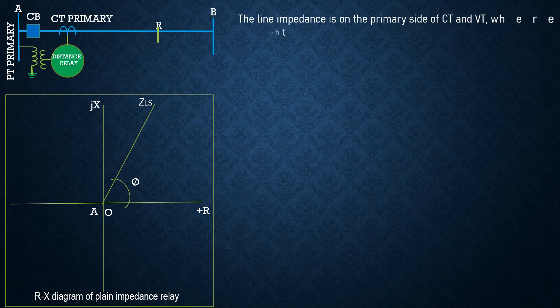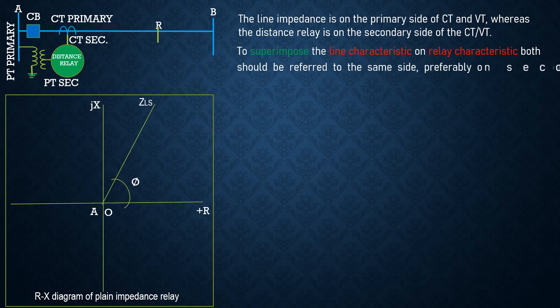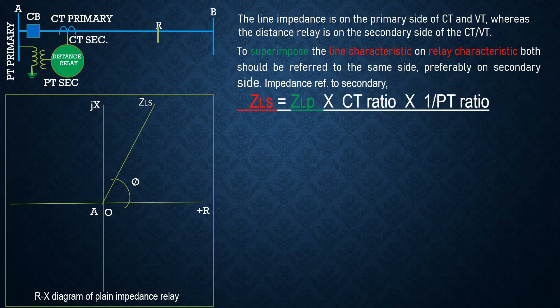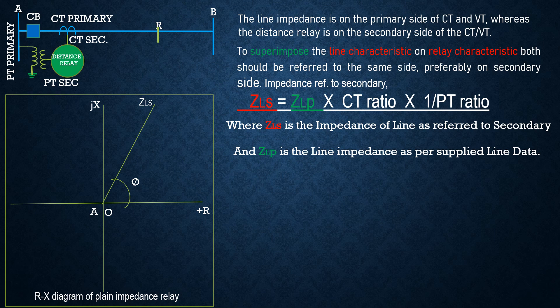The line impedance is on the primary side of the CT and VT, whereas the distance relay is on the secondary side. To superimpose the line characteristics on the relay characteristic, both should be referred to the same side — preferably the secondary side. Therefore, the impedance of the primary as referred to the secondary is: ZLS = ZLP × (CT ratio) × (1 / PT ratio), where ZLS is the line impedance referred to secondary and ZLP is the impedance from the supplied line data.